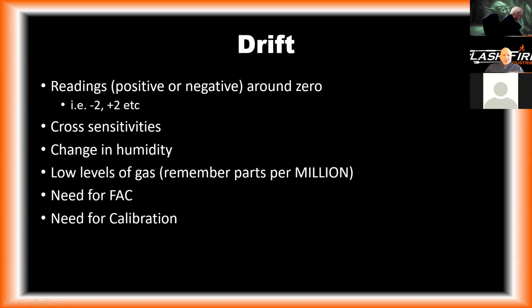But again, if we get drift, we're not taking the meter out of service and calling me. This is the first thing that we're doing, fresh air calibrating. If it continues to drift after that, now maybe we're going to take it out of service. But the first thing is fresh air cal.